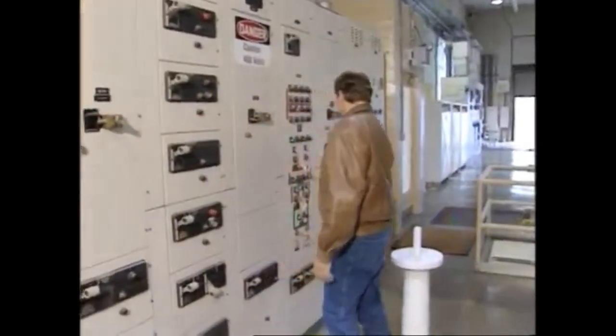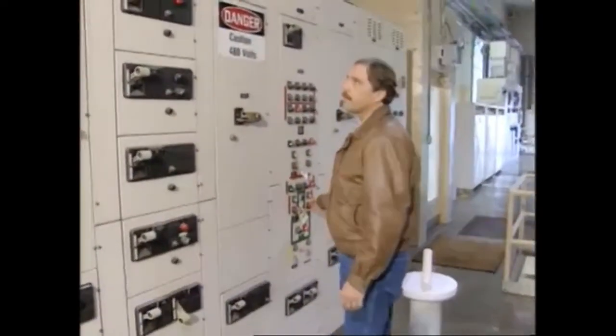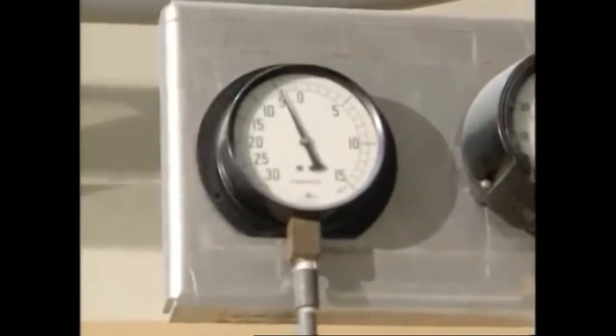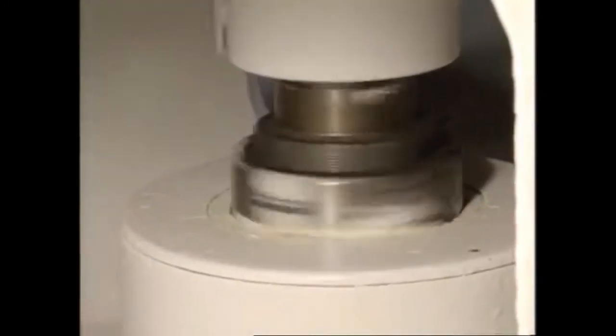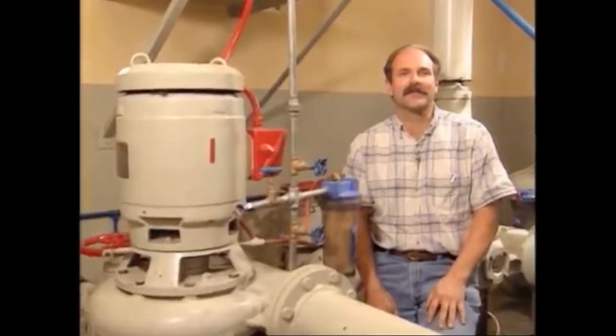Single phasing refers to the condition that occurs when one phase of the power source to the motor is lost. When that happens, an induction motor will continue to rotate, but characteristically with increased noise, vibration, and motor heating. Determine if a single-phase condition exists. We could contact the utility company, or we could look inside the motor control center to see if a fuse is blown or a circuit breaker is tripped. Then we could correct that problem. Another method of preventing that problem would be a three-phase monitor.